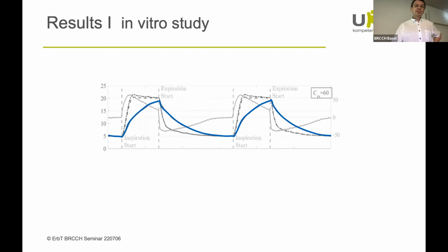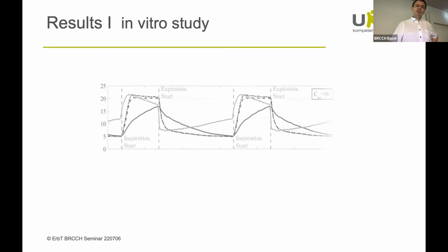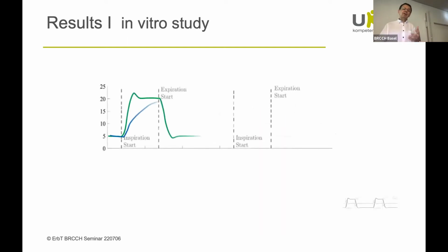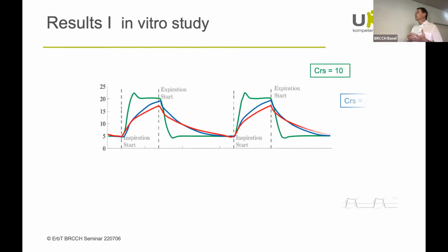The tracheal pressure has a completely different course from the one that's indicated in the ventilator. And this is even further deviated when you have the condition of a really high compliance, such as situations with patients with emphysema.